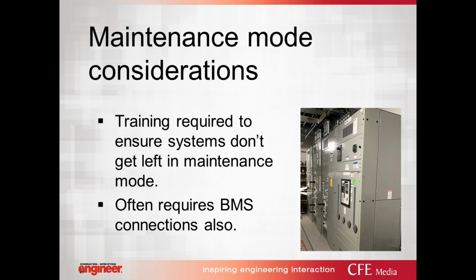Thank you, Zia. Some of the considerations that we need to work with on maintenance mode considerations is that there will be additional training required for personnel for use of that system. It is not a hands-off system as others might be. The gear can get left in a maintenance mode if we don't have some type of BMS connections, or if we don't have a procedure for ensuring that gets taken care of. Also, a lot of the times we have a situation where our remote controls are at entrances of rooms for safety considerations. So therefore, we need to very much consider lockout tagout if these types of remote controls are used.